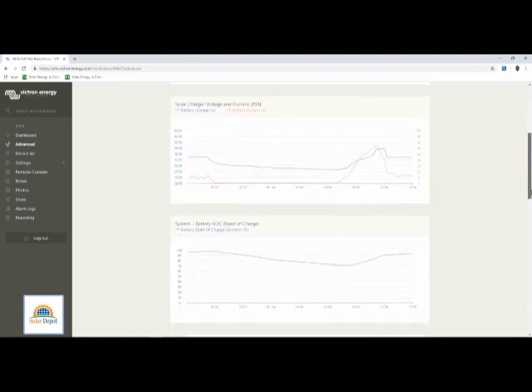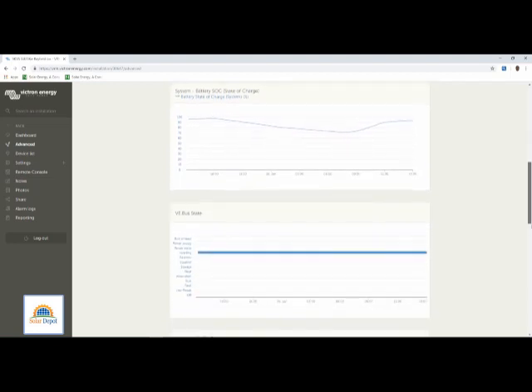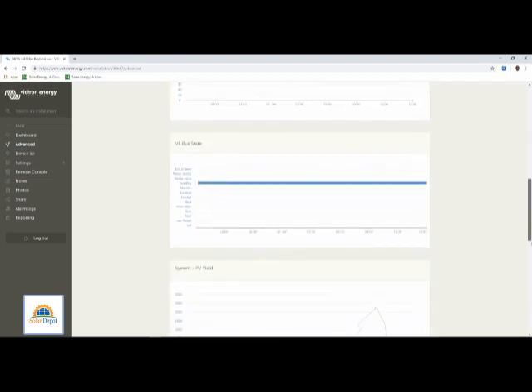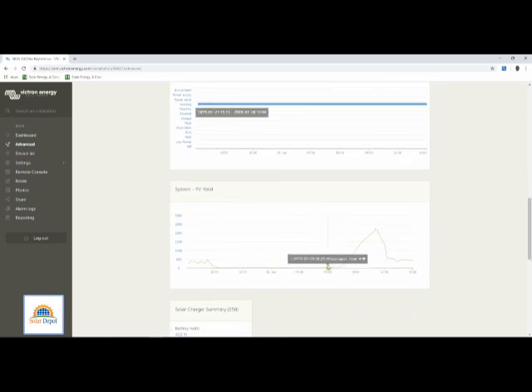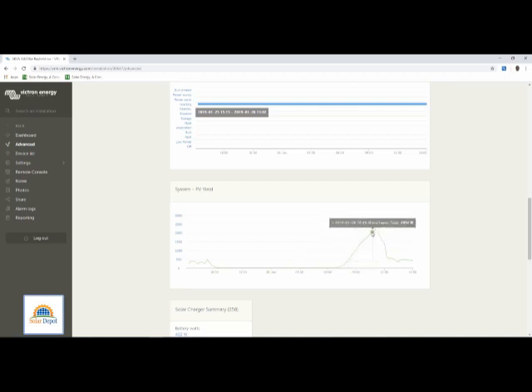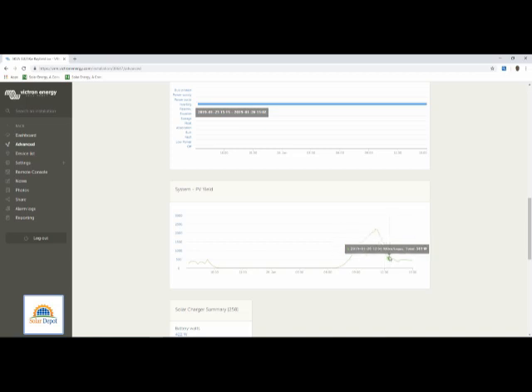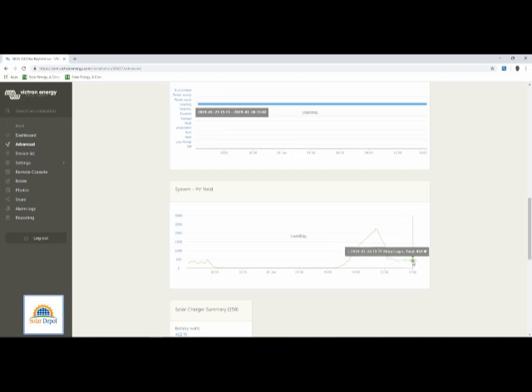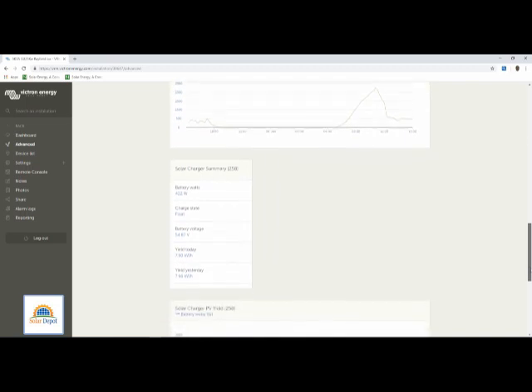You can see the solar charger voltage and current, battery state of charge, and PV yield. Starting from 6 AM, the PV yield was 0W meaning that the environment was still dark, there was no solar energy generated at that time. It peaked at 11:01, meaning that was the peak capacity of the solar generation that day at 2,241W. Now at 15:00, the PV yield is 422W because the battery is already at the absorption stage and little current is trickling into the battery.